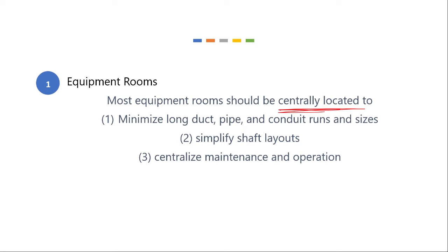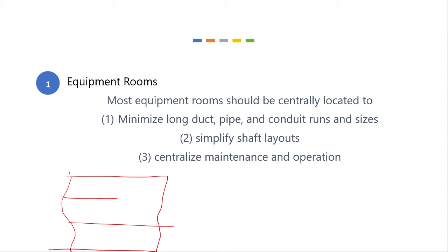And by centrally located, I mean we're trying to minimize the length of the duct, the pipe, and the conduit runs and sizes. So most equipment rooms should be centrally located to minimize long duct, pipe, and conduit runs and sizes.